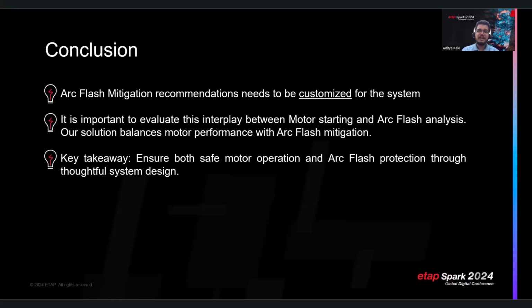In conclusion, I want to emphasize that the arc flash mitigation recommendations have to be customized for each system. It's also important to evaluate the interplay that we saw here between motor starting and arc flash analysis. The solution that we present here balances the motor performance along with the arc flash mitigation. So the key takeaway here: ensure safe motor operation, safe motor starting, along with arc flash protection through thoughtful system design.